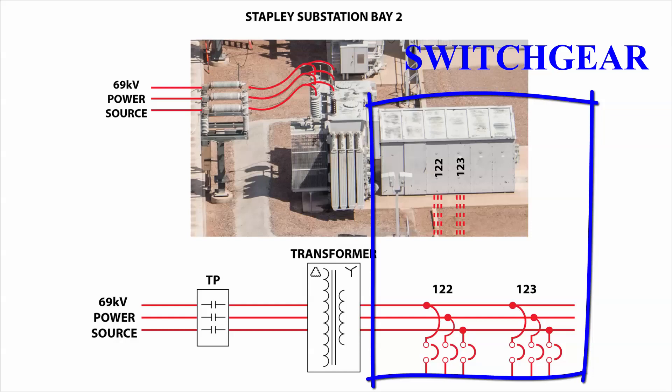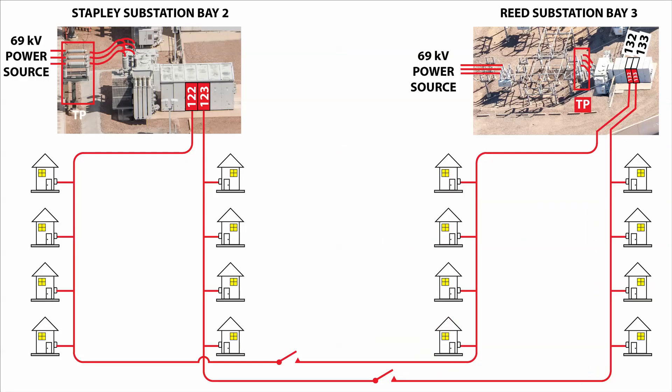Some of the three-phase 12 kV power coming out of the substation is connected to industrial and commercial customers. For residential customers, the three-phase 12 kV circuit is split up into three separate conductors. The individual conductors are energized at 7.2 kV to ground and branch out through neighborhoods. Small transformers near homes which convert the 7.2 kV to 120 volts are not shown here to simplify the drawing.